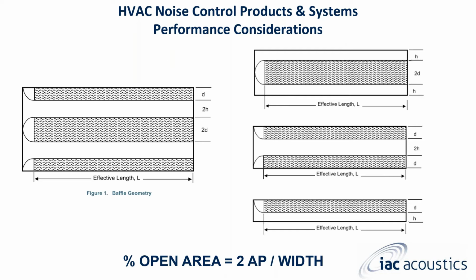So the number of baffles and air gaps only affects the flow area, as does the height and the span of the baffle. Having more baffle arrangements within the silencer gives you more flow area. You will then also have lower air gap velocity and lower pressure loss.